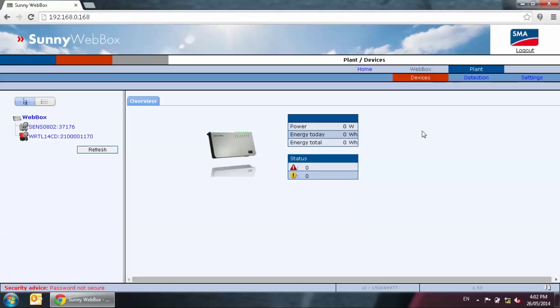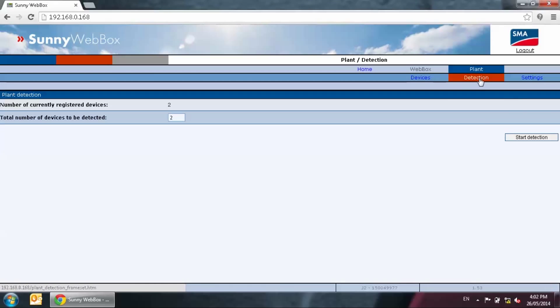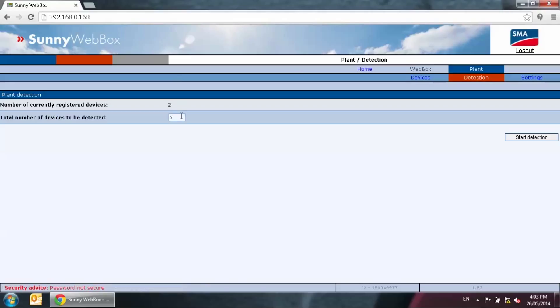The web box is not counted as the device itself as we are logged in already. A device is an inverter, a sensor box, a meter connection box. If you have 2 inverters and 1 sensor box in your system, you will need to put in 3 in the number of detection field. Here we will only put in 2 as we have 1 inverter and 1 sensor box connected. So we type in 2 and then press start detection.